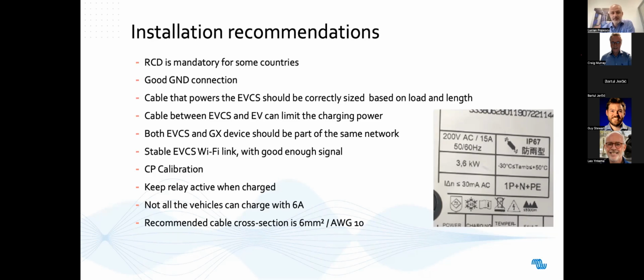Question: how many ohms is a good ground? There was an answer from the chat saying less than 4 ohms is according to EU regulations, but recommended to be as low as possible. It's recommended to stay lower than the regulation for that country. When you're consuming a lot, you might see that the voltage of the ground isn't zero anymore — that's the first sign you should think about the quality of the ground installation. Make sure it's correctly measured; there are devices that do certification for ground connections, so make sure your ground is correctly made and certified.